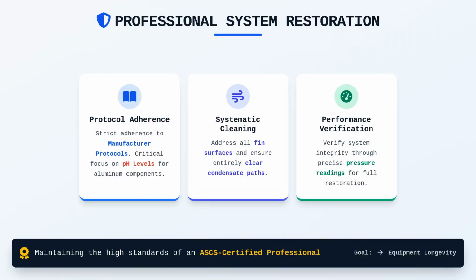The complexity of these systems means there is no shortcut to thoroughness. Every manufacturer provides specific maintenance protocols that you must adhere to, particularly regarding the pH level of the cleaners being used on aluminum components. By systematically addressing the fin surfaces, ensuring clear condensate paths, and verifying performance through pressure readings, you elevate your practice from mere cleaning to professional system restoration. These methods ensure the longevity of the equipment and uphold the high standards expected of an ASCS certified professional in the field.